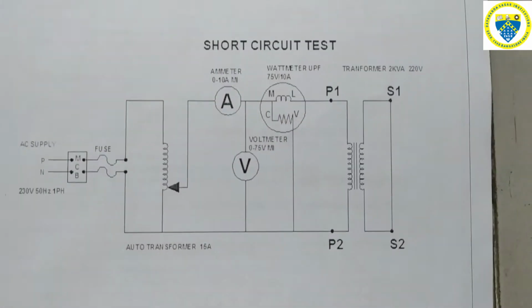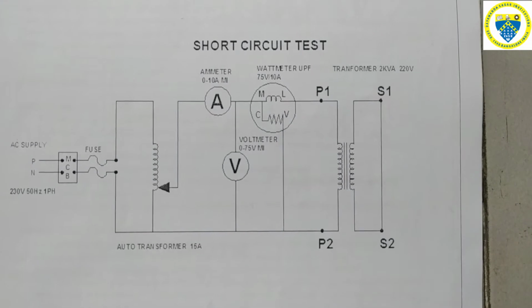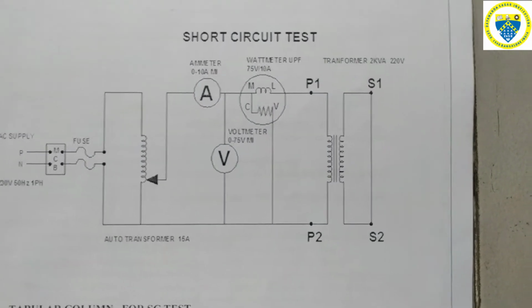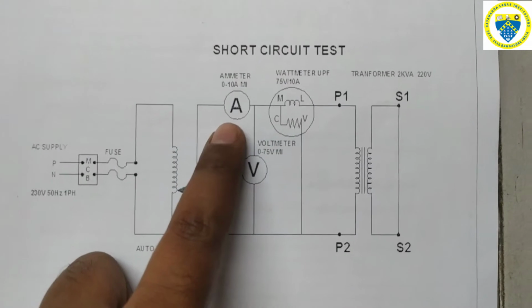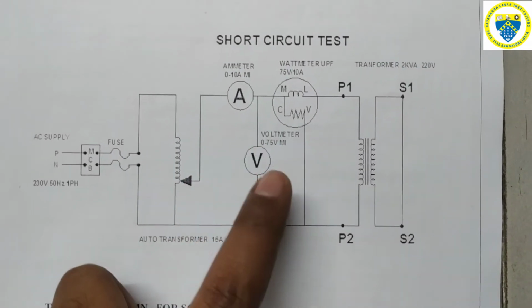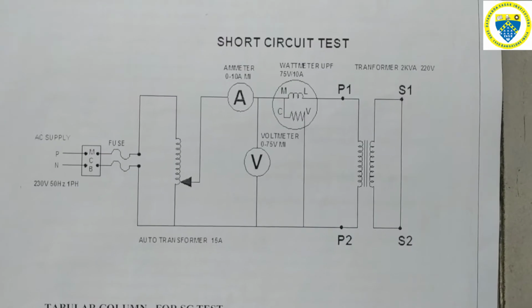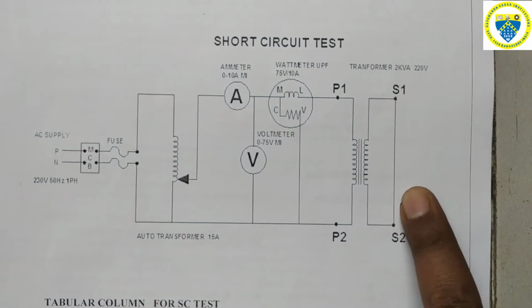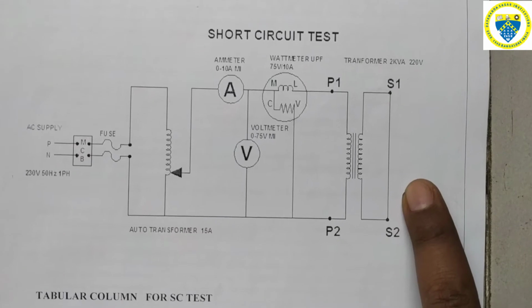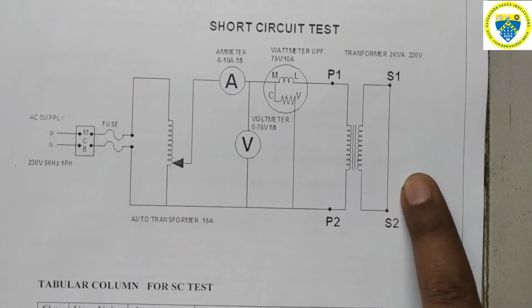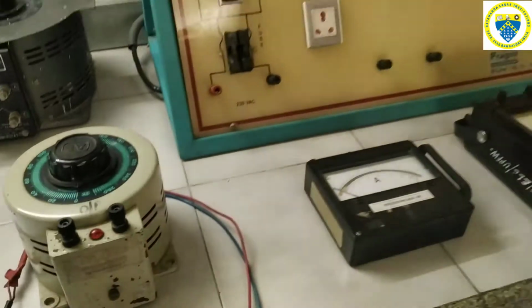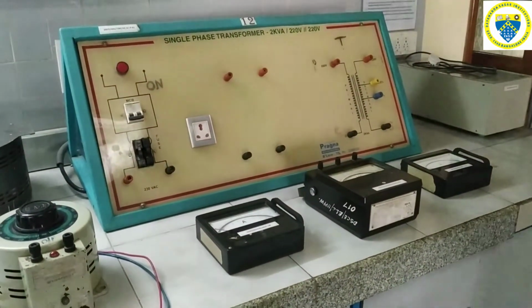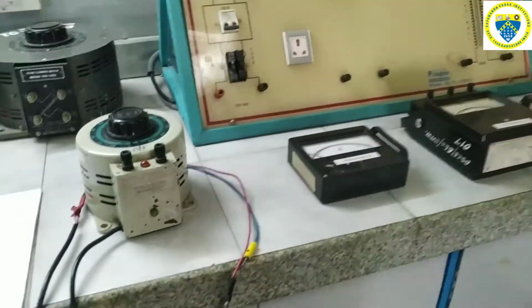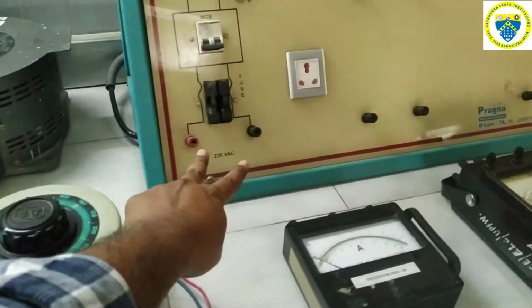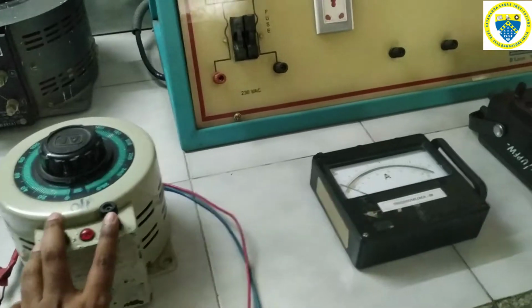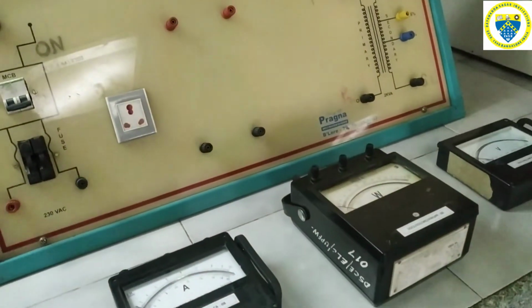Here we are using a unity power factor wattmeter with a rating of 75 volt and 10 amperes, an ammeter with a current range of 0 to 10 amperes, and a voltmeter of 0 to 75 volt. In this connection the secondary of our single phase transformer should be shorted, S1 S2. So this is the overall setup for the short circuit test on a single phase transformer. This is an auto transformer to which a supply will be given. From the auto transformer the supply is given to the transformer under test.